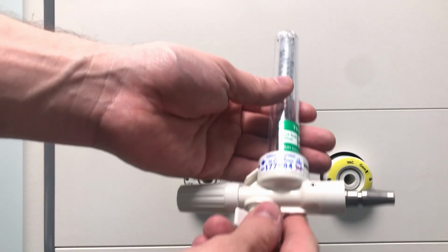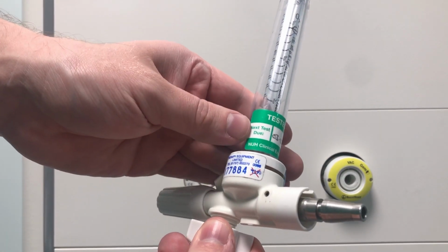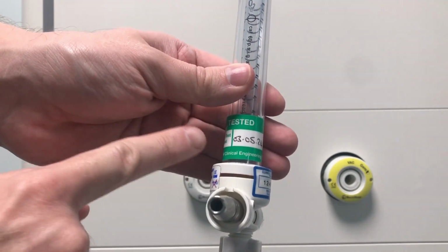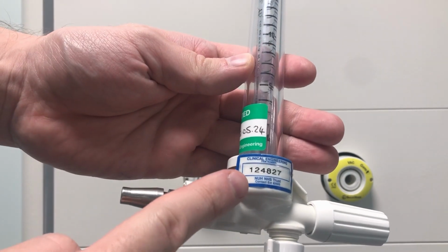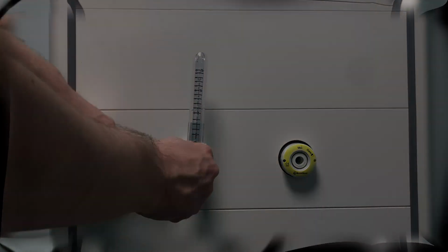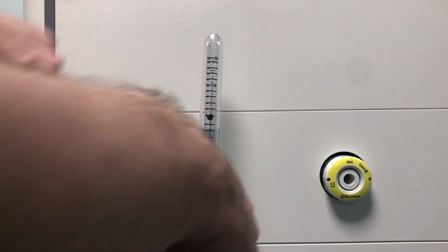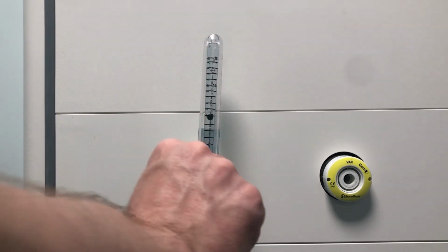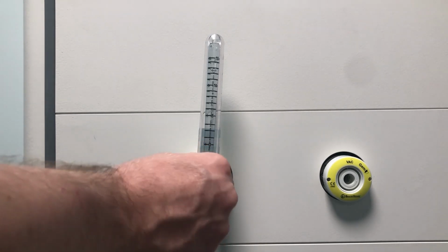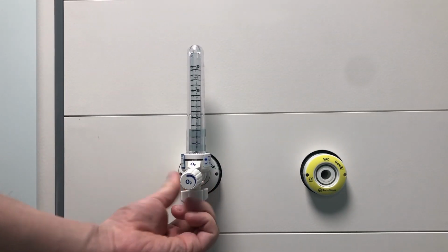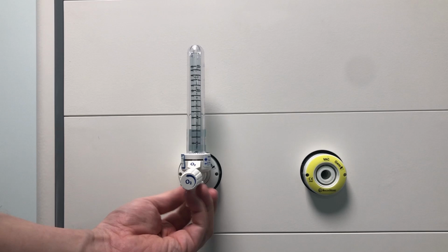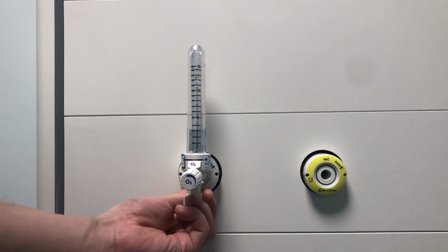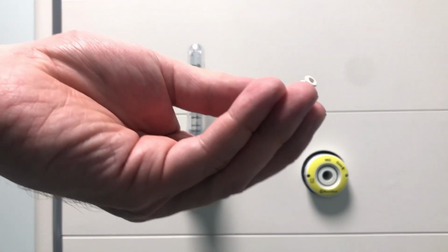So initially there are some pre-operational and daily checks. The service date, ensure that it has one, and an MESU sticker. Ensure the flow meter is off and the ball indicator is at 0. Turn the flow on to 5 litres, ensuring indicator ball rises. Check the white connector at the base of the flow meter is correctly fitted and isn't cross-threaded or damaged, and ensure all connections are tight and leak-free.